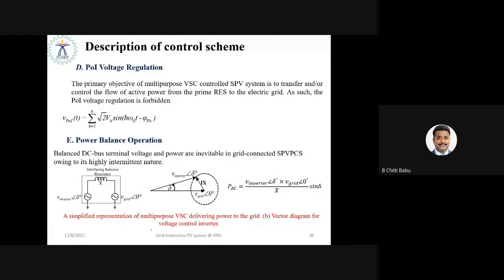We assume that it is like an actual power system, where power is transmitted from the sending end to the receiving end, having the inverter voltage with the angle delta and the receiving end voltage V grid at a zero angle. So due to the phase angle difference, power flows from the sending end to the receiving end through a line reactance of X. The output power is inversely proportional to the line reactance, so that we can model a grid connected solar PV as a typical power system model.